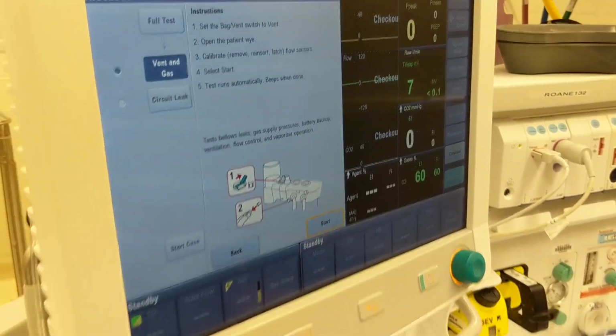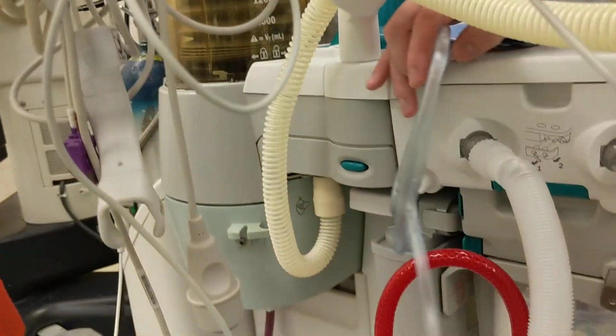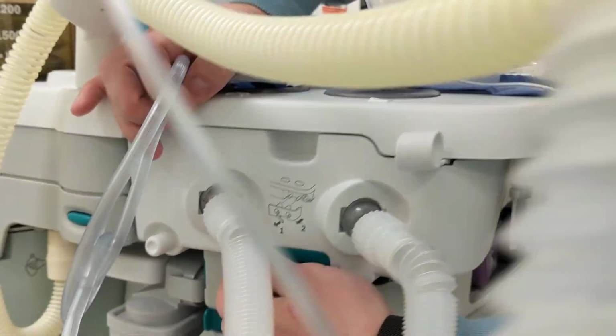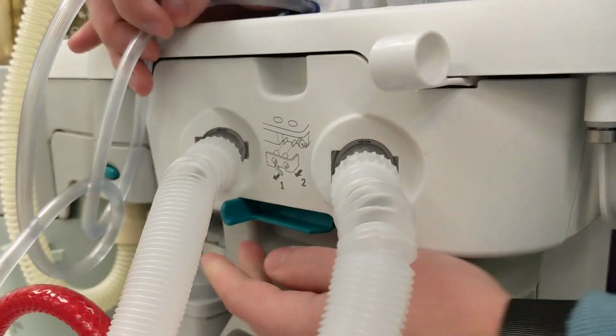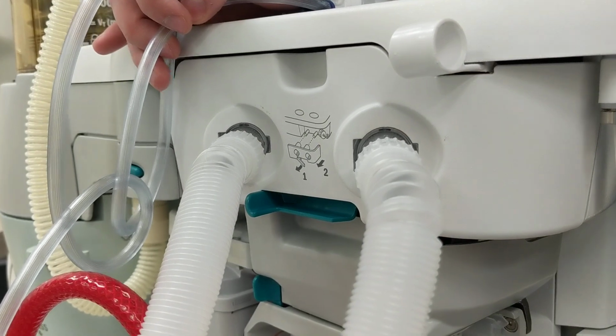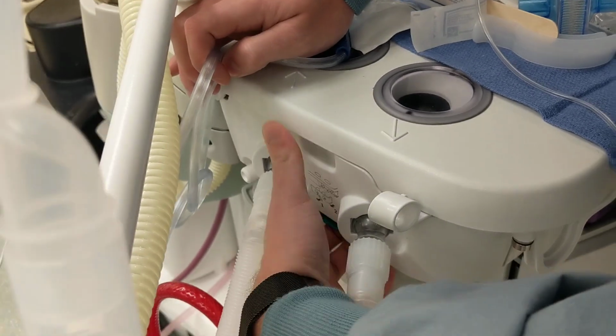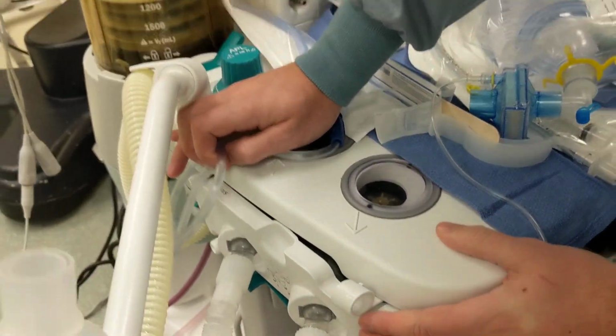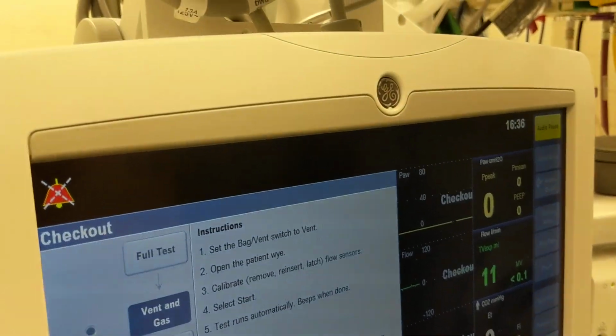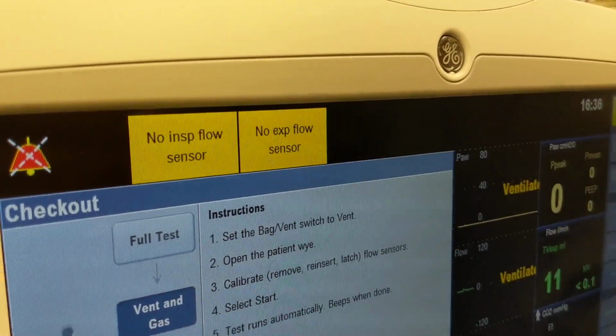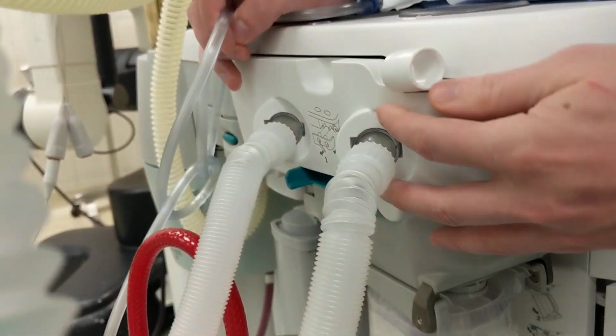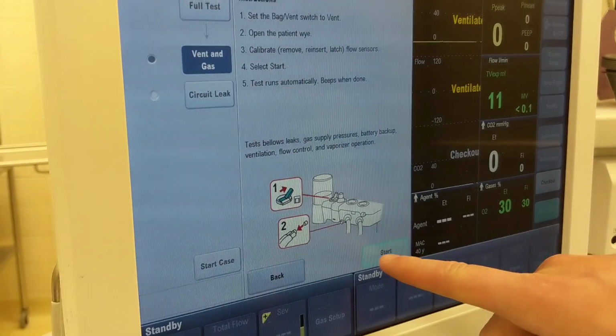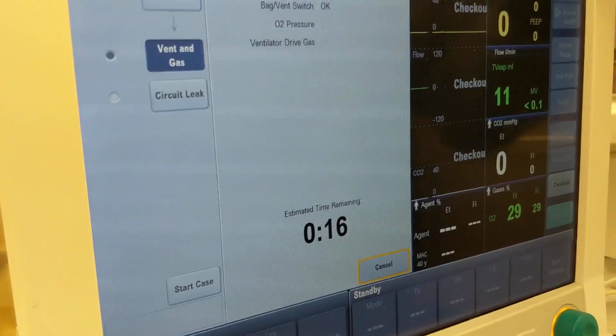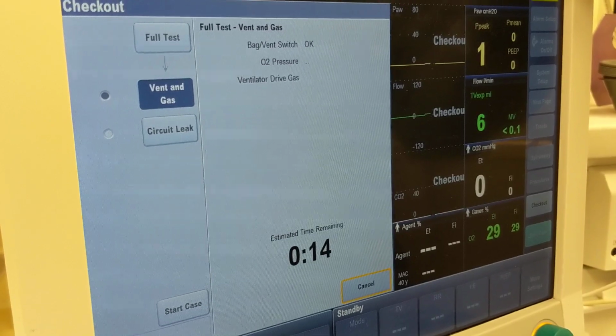Third step, calibrate to remove the flow sensors. So we go back to where we changed out the CO2 absorber, and there's another latch here that we can take out, right just here on the above side. To take it out, it comes out all the way, but it's easier to just give it a little pull out, just about an inch or so, to expose this. And then we look back on our screen. And once these two yellow boxes pop up, we can just go ahead and put it back and relatch. And now we're ready to hit start and let the machine do its checkoff. The first step is fairly brief.